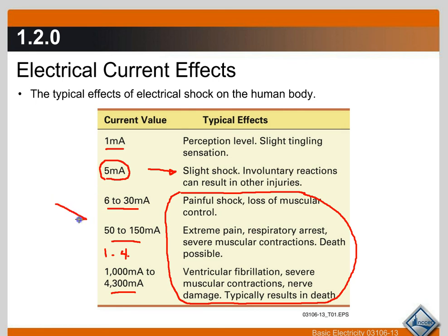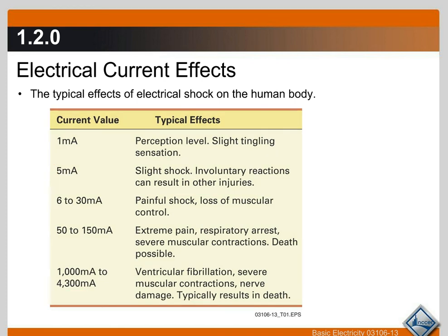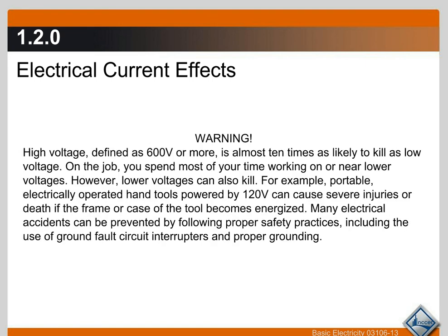You need to be extremely careful. We tend to get complacent — we work around it all the time and don't take the time to go shut the units off and double check everything. You really need to make sure that you do that. At 600 volts and 480 volts, that ups the chances of it killing you if you get tagged. We spend a lot of our time with our hands in residential equipment, which is 120 to 240 volts, but those can get you too if you have broken skin, a cut on your hand, if it's wet outside, if you're kneeling on the ground without rubber soles insulating you and the ground is damp. Even on residential systems, you're paying attention — can't stress this enough. Shut off the electricity at the source. That means you go to the disconnect at the unit so you know for sure that it's off, not just the circuit breaker inside the house.